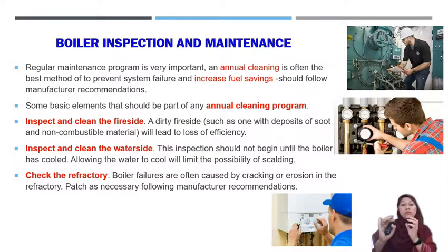When all the water becomes steam, you need to look at both sides, and also check the refractory. Refractory involves the container itself, the vessel itself, because we produce high heat, high temperature, high pressure.